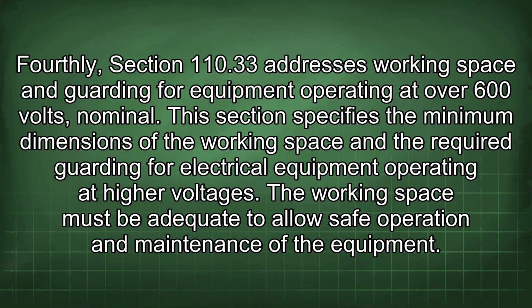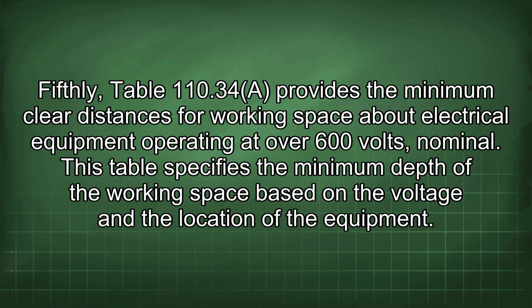Fourthly, Section 110.33 addresses working space and guarding for equipment operating at over 600 volts, nominal. This section specifies the minimum dimensions of the working space and the required guarding for electrical equipment operating at higher voltages. The working space must be adequate to allow safe operation and maintenance of the equipment. Fifthly, Table 110.34 provides the minimum clear distances for working space about electrical equipment operating at over 600 volts, nominal. This table specifies the minimum depth of the working space based on the voltage and the location of the equipment.